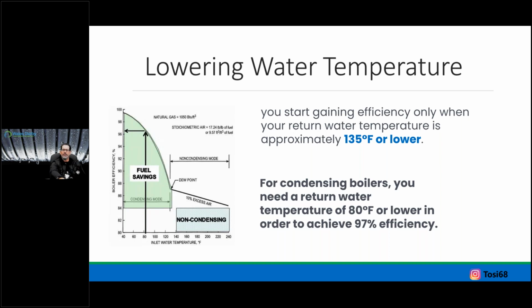How about change it just a little bit, and you're going to see some really big changes, like, wow, I don't get those nuisance calls. I don't have to go out there in the middle of a winter night because electrodes have failed. And then what is the idea? It's like, well, do you investigate what is the failure? Why is this happening? Check the venting out. Look at your venting. Now, natural gas over LP might have another set of rules as far as the products of combustion, but that's for another day.